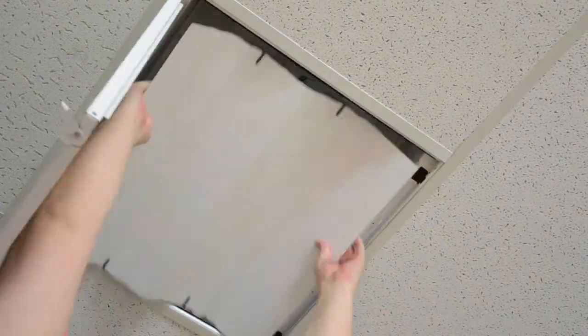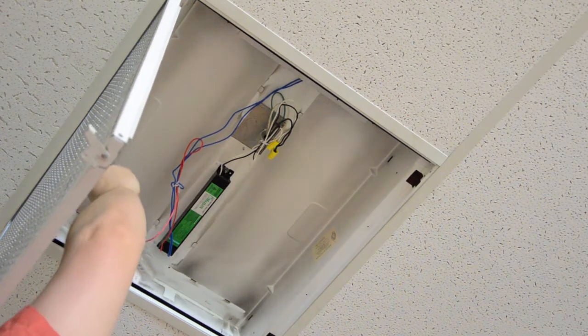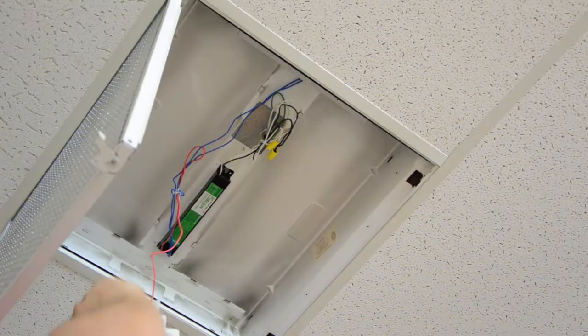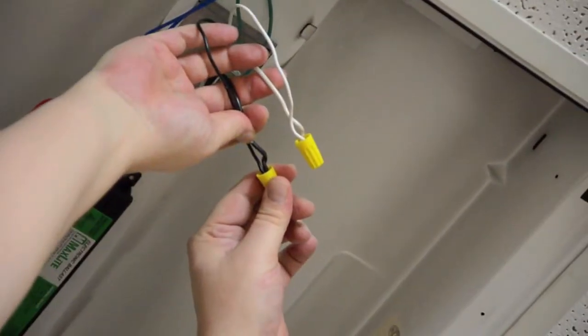Shut off all power to the fixture. Remove the tombstone fluorescent sockets and the socket holder bracket they are mounted to. Remove the ballast cover, disconnect the main power from the ballast, and remove the ballast from the fixture.